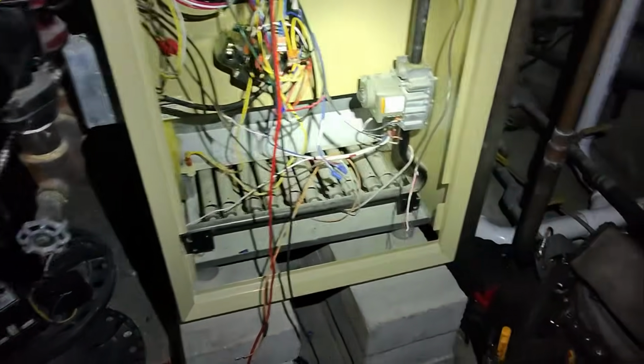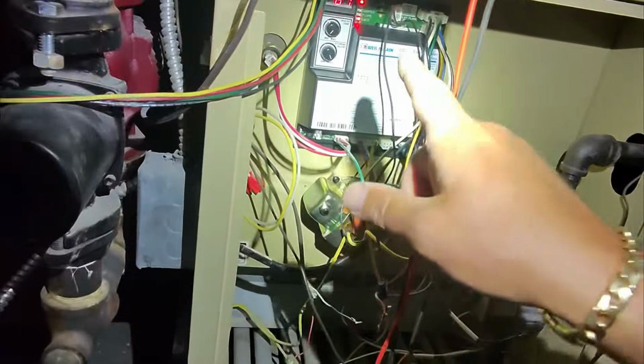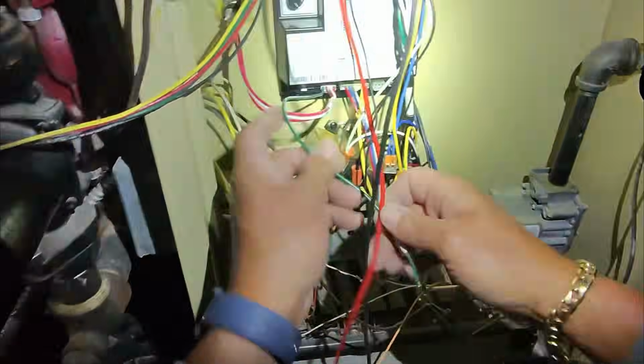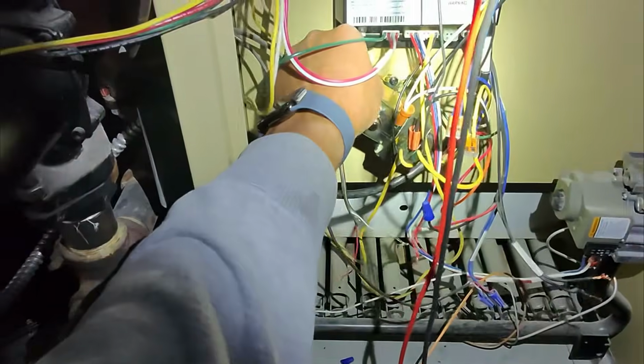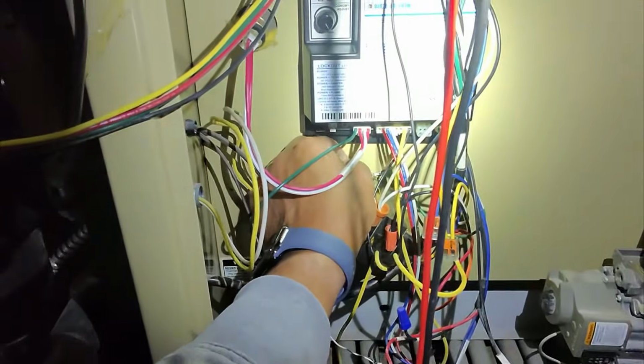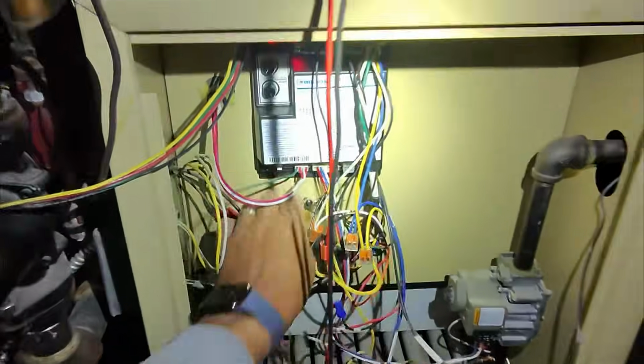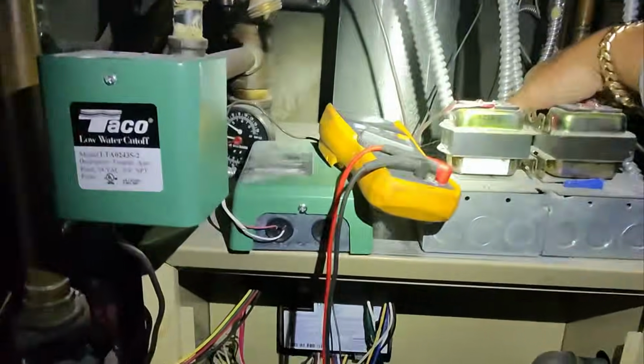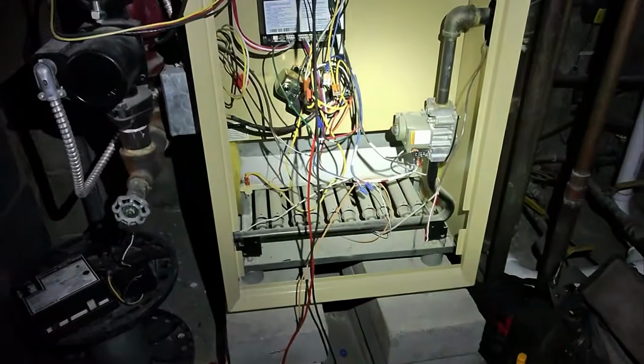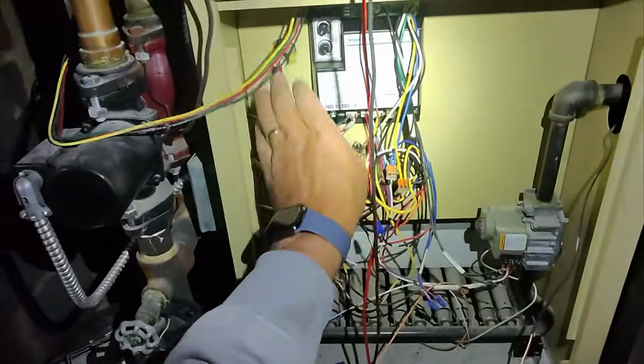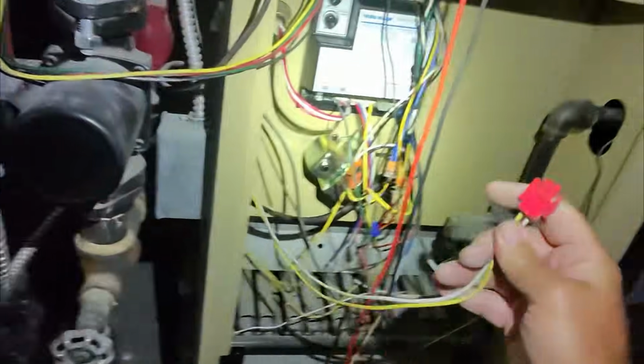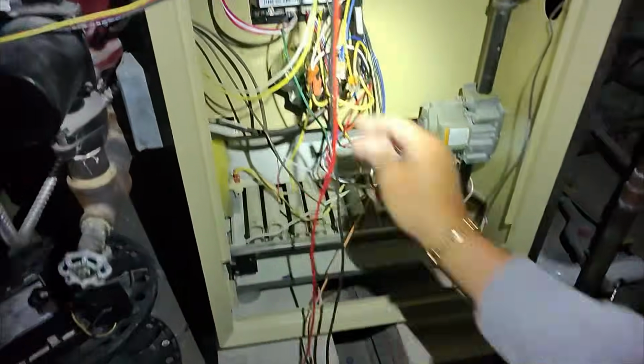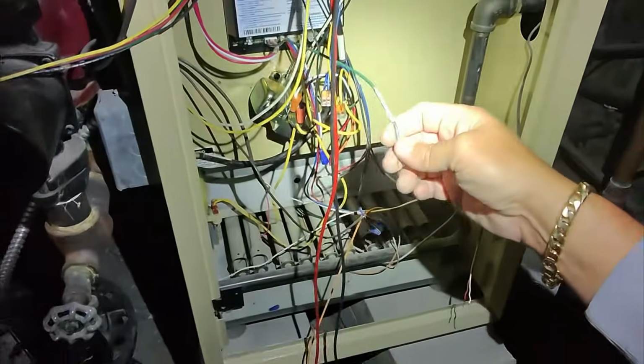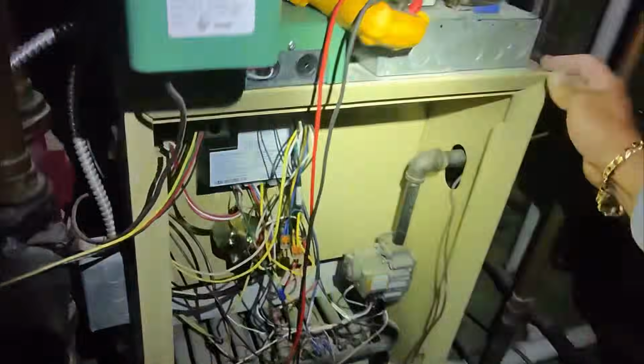All right, so I still have a low water cutoff error there, but I think it needs a ground. Yeah, see that? It needed a ground. All right, let's get some sheet metal screws from the truck, and then we got to figure out what the hell's going on here and why this, whatever this is, is doing. Let's plug that back in. That's the circulator. We need to get a sheet metal screw, hook up this to our ground for our low water cutoff, and now start troubleshooting electrical issues.